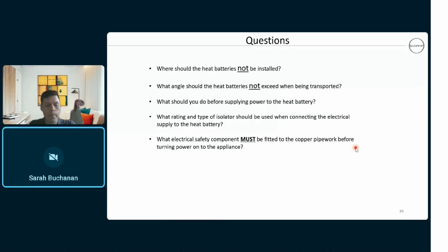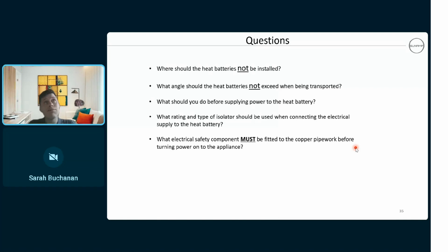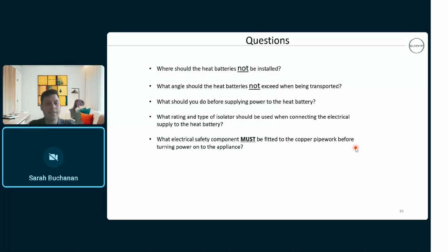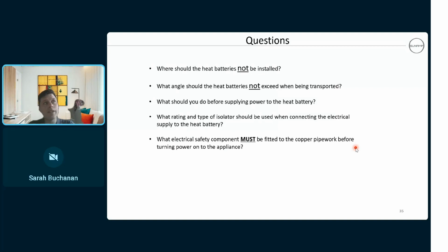Someone's asked, can additional insulation be added to the outside of the unit? You can, just wrap it in glass wool. There's nothing wrong with that. It's not going to affect the unit in any way and there are no ventilation requirements. It's not a question I've been asked before, actually. That's a good one. But if you ever have to work on that unit for whatever reason, you've just got to take that insulation off. So we'd probably be saying no to that.